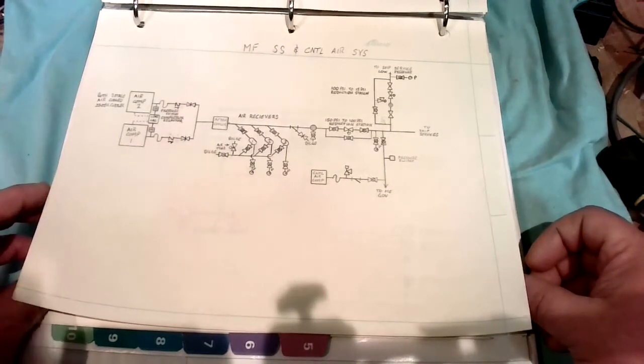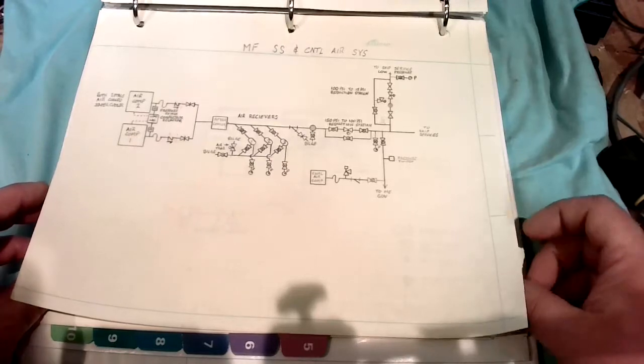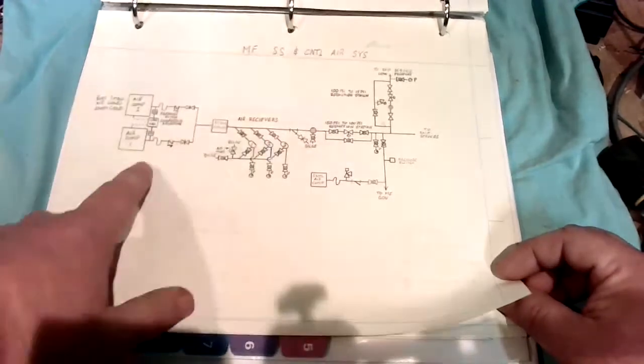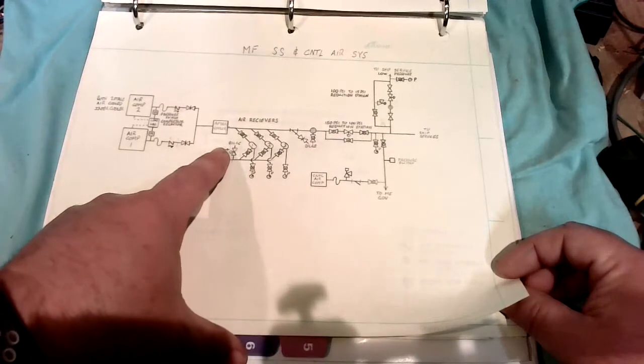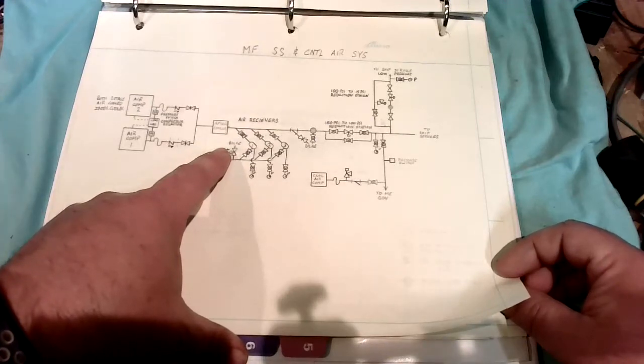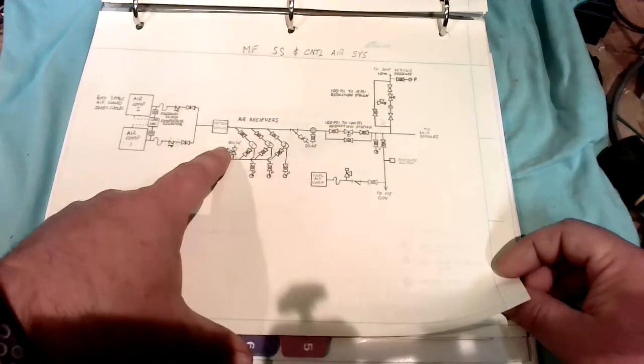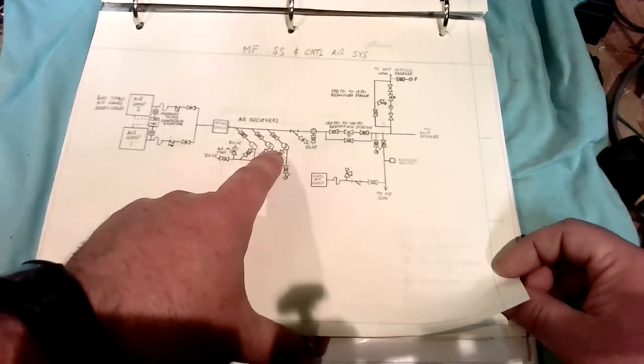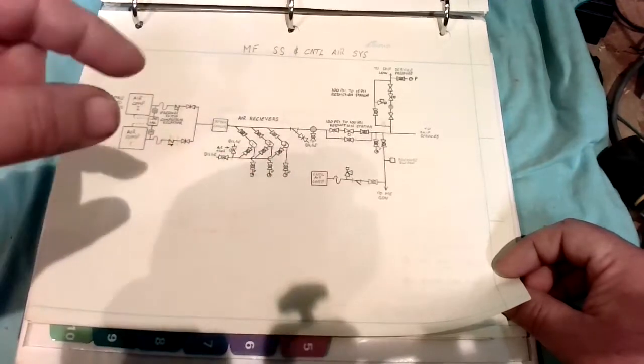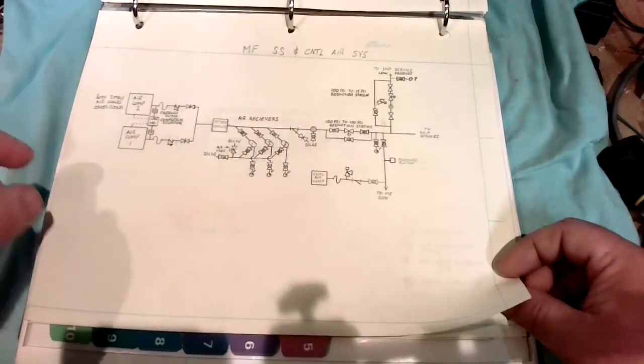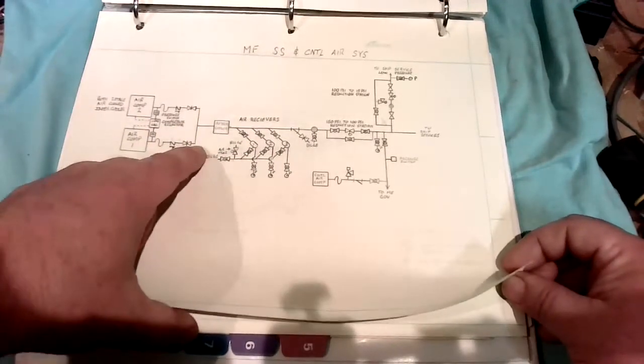So this is our air compressor system. So ship service air and control air. When you start a diesel engine this size, you're not just turning a key. You are literally pushing a button, and that button is opening up a valve to allow air pressure, pneumatics, to go in, and it's air pressure that pushes on the pistons and gets them starting, and then you switch over to fuel. So that's what we've got here.